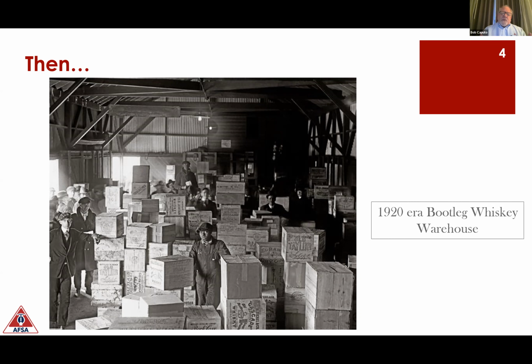So in other words, when we have a fire, we have a fuel load that creates a heat release rate. The higher the heat release rate, the greater demand for water so that the sprinklers can control the fire or perhaps suppress the fire. So in this picture, we're looking at 1920 era storage that was relatively low. And you can see these whiskey bootleggers only stack these boxes as high as they can reach above their head.